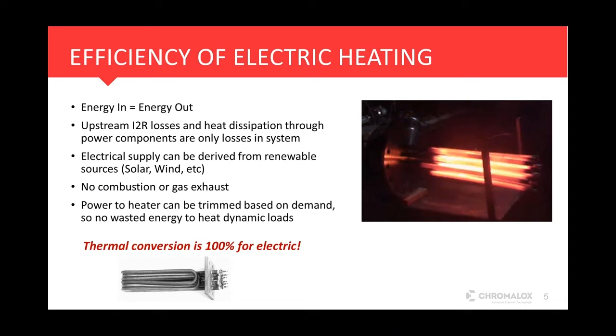So that's basically what it is and how it's controlled. We ask ourselves, how efficient are electric heaters? The answer is pretty simple: they're very efficient. The energy that's applied to the electric heater is entirely converted to heat at the heater. Upstream, you do have what's called I squared R losses and heat dissipation through some of the power components, but those losses are really negligible to the point that you're still operating up into the higher 90 percentile for efficiencies with these systems.